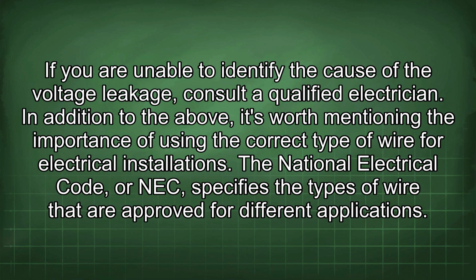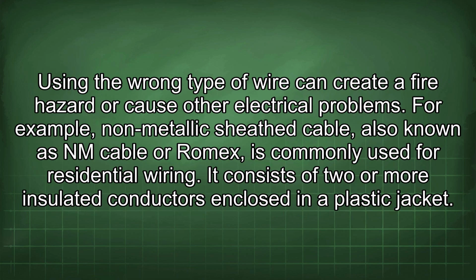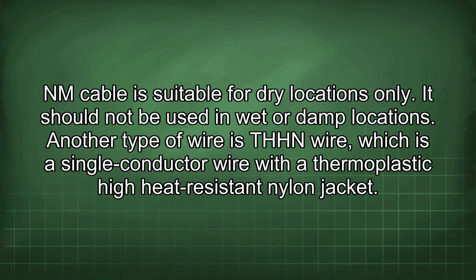In addition to the above, it's worth mentioning the importance of using the correct type of wire for electrical installations. The National Electrical Code, or NEC, specifies the types of wire that are approved for different applications. Using the wrong type of wire can create a fire hazard or cause other electrical problems. For example, non-metallic sheath cable, also known as NM cable or Romex, is commonly used for residential wiring. It consists of 2 or more insulated conductors enclosed in a plastic jacket. NM cable is suitable for dry locations only. It should not be used in wet or damp locations.